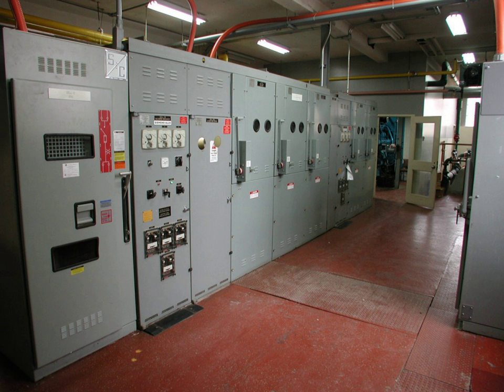The construction features of an electrical room vary depending on the scope of the equipment to be installed. Floors may be reinforced to support heavy transformers and switchgear. Walls and ceilings may have to support a heavy cable tray system or busbars. Additional ventilation or air conditioning may be needed, since electrical apparatus gives off heat but the temperature must not rise beyond the tolerance of equipment.